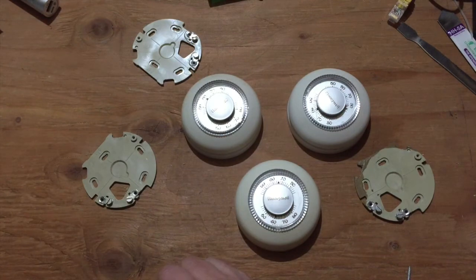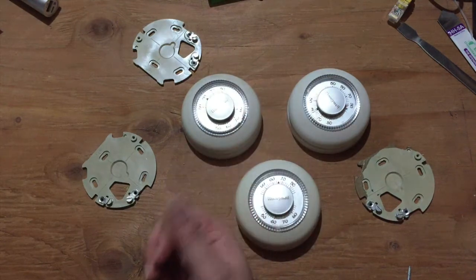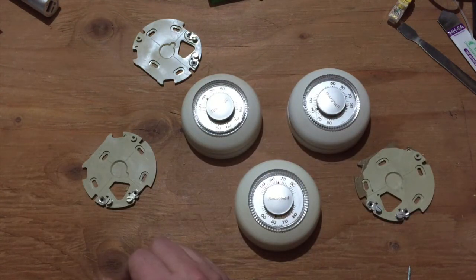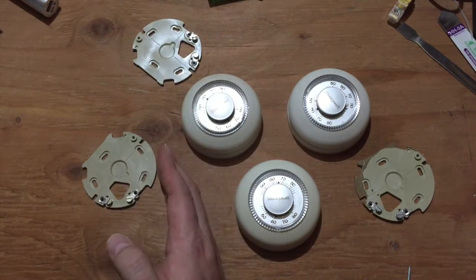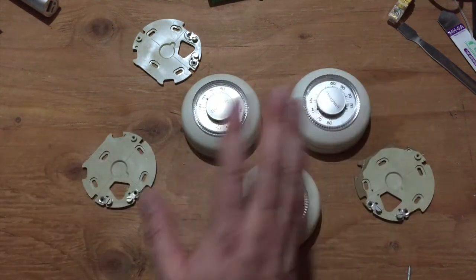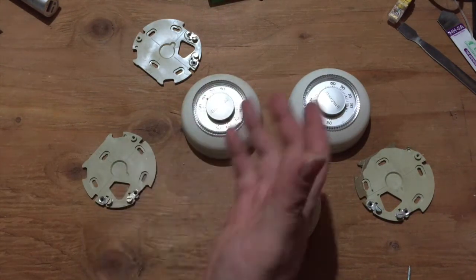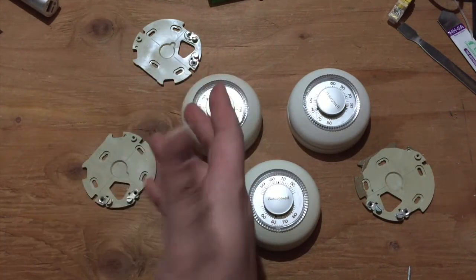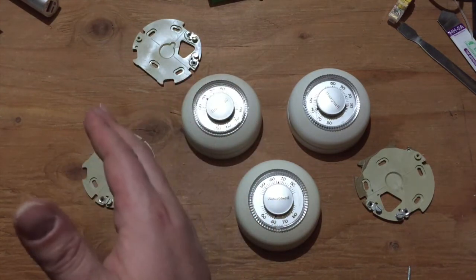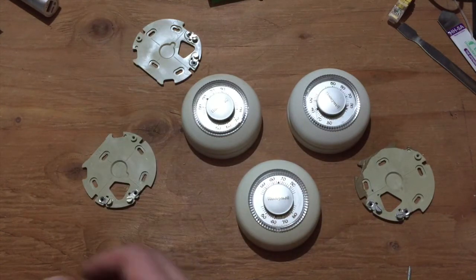So you have a lot of functionality there, and then there's a really rich set of overrides that are available when that schedule isn't enough. So there's the basic permanent override. You can say set the temperature to this exactly until I say otherwise. But you can also do timed ones. So set it to this for 2 hours, then go back to your program. You can do a non-time based temporary one, like set it to this temperature, but then when the schedule would set it to a different temperature, go back to that automatically. Anytime you can manually resume and go back to the program.